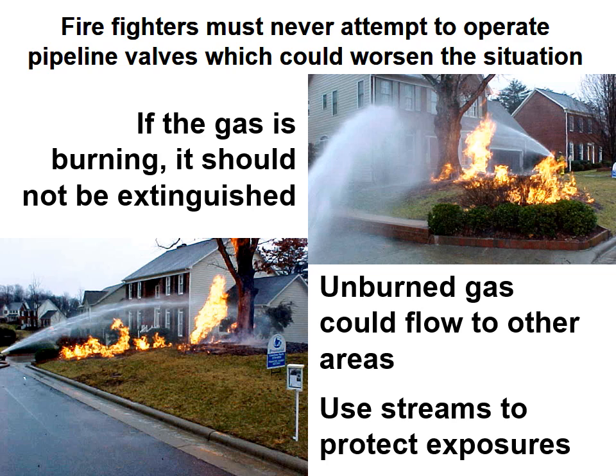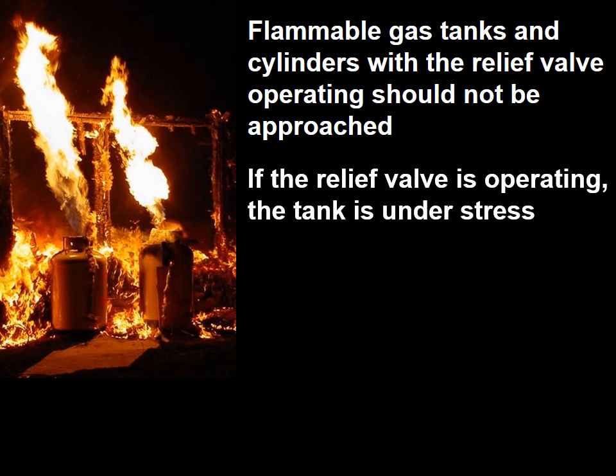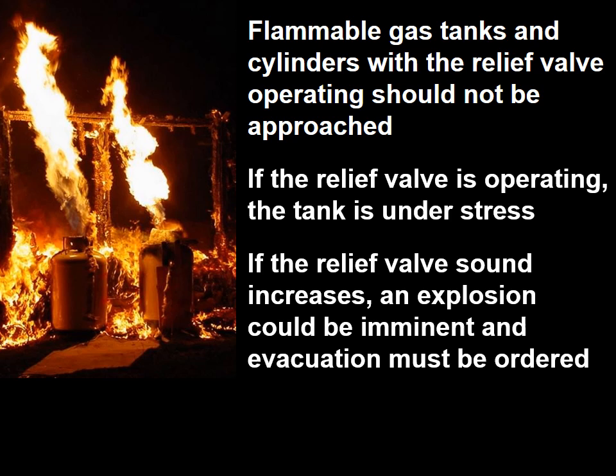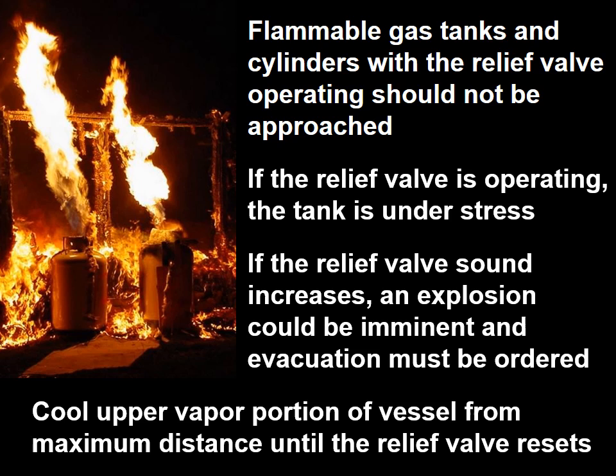Use streams to protect exposures. Flammable gas tanks and cylinders with relief valve operation should not be approached. If the relief valve is operating, the tank is under stress. If the relief valve sound increases, an explosion could be imminent, and evacuation must be ordered. Cool the upper vapor portion of the vessel from the maximum distance until the relief valve resets.